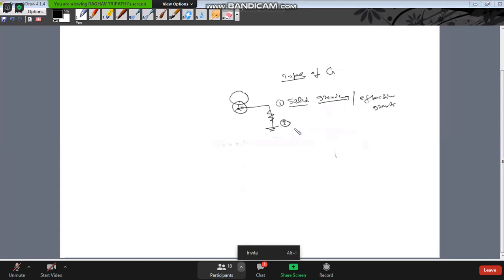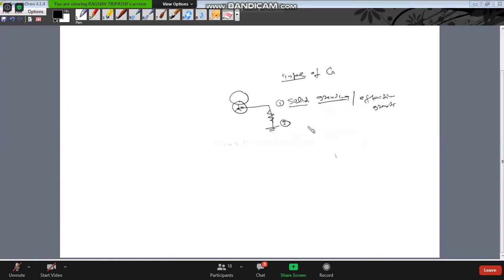And the second method for the grounding is resistive grounding. For resistive grounding, we use the NGR, neutral grounding resistor. This kind of grounding we generally select for generating power stations. In some substations also this type, NGR, is preferred. In our substation, we are using NGR.